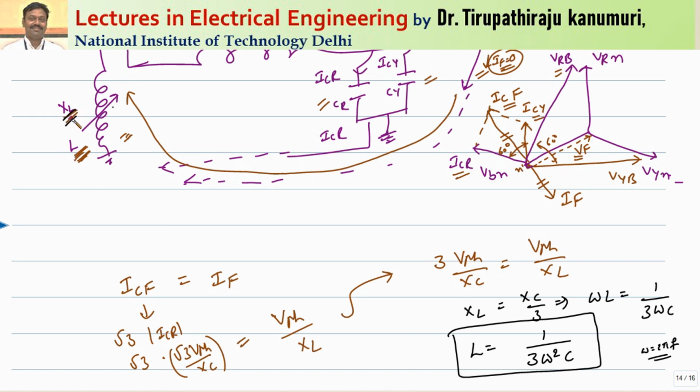And when this reactor will operate, only if the B phase is connected to ground, as this voltage is now become equal to ground voltage, or at this point now the voltage becomes equal to your B phase voltage. So because of this voltage, the current is passing in such a way, this current will be exactly counterbalancing the value of the capacitive currents. So that's why this is called as arc suppression coil.